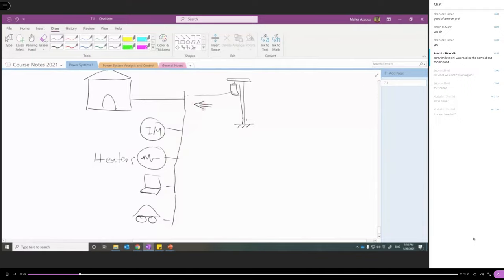And if you want to calculate the equivalent impedance, this is near impossible. We cannot do that. Every impedance here is variable, and those impedances are nonlinear. They depend on the voltage, the frequency of the supply. So it is not practical or possible to represent the load using a constant impedance. So how we represent loads in power system analysis: we typically represent them using their active and reactive power consumptions. And those active and reactive power consumptions could be variable depending on the voltage, as you will see.